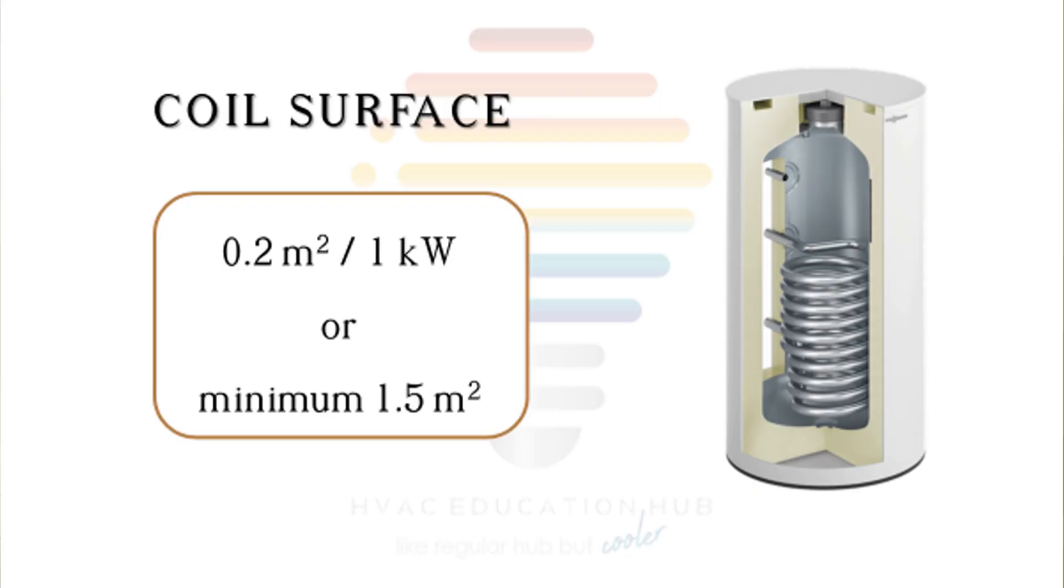First thing to remember is that in order to have quality domestic hot water tank heating with heat pumps, you need to have big coil surface of tank. For example, 0.2 square meter per 1 kilowatt, or for small models, minimum 1.5 square meters of coil surface.